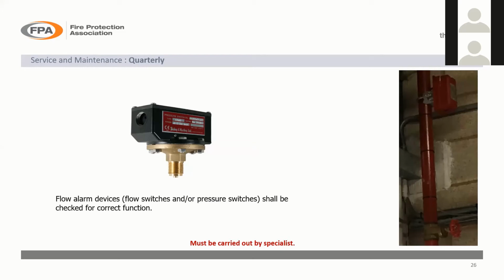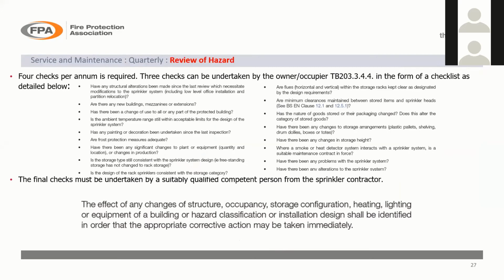So on a quarterly basis, flow switches need to be tested, and obviously if you've got something like a multi-storey office block divided into zones with a flow switch on each one, if you've got a 60-storey building and there's 4 on each zone, that would be 240. It can be a laborious undertaking, but it needs to be undertaken by a specialist. It's not something you can carry out in-house.